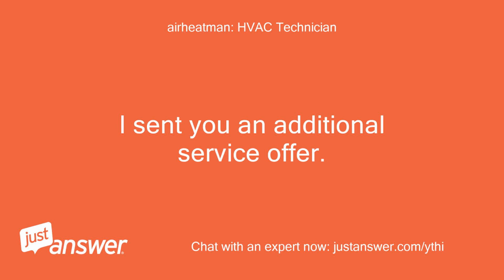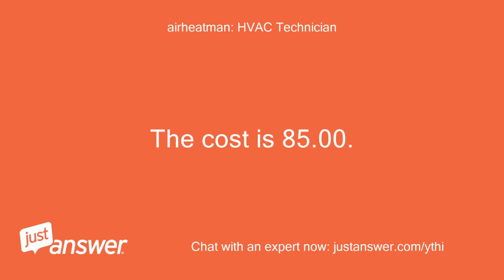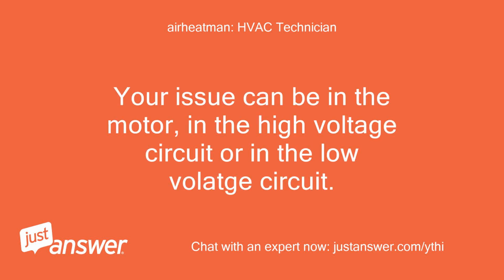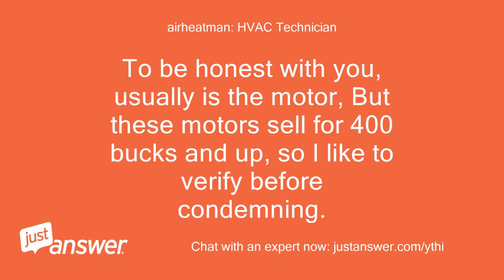I sent you an additional service offer. The cost is $85.00. Your issue can be in the motor, in the high voltage circuit, or in the low voltage circuit. To be honest with you, usually it is the motor, but these motors sell for $400 and up, so I like to verify before condemning.